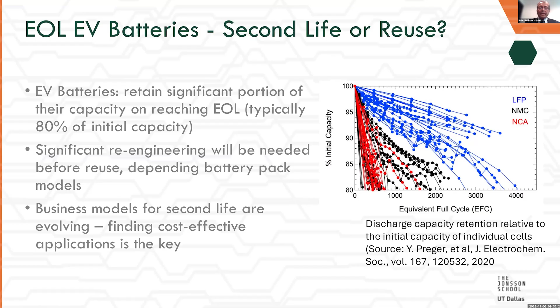But there are common challenges with reuse. We don't know the state of health of the batteries; it varies from cell to cell, sometimes module to module, and cells degrade variably in many cases. You need to look at cell balancing issues, which leads to pack-level stability concerns, so you have to ensure performance is stable from a battery pack. Most of the time, these battery packs are packaged with a proprietary BMS, a battery management system essentially needed for lithium-ion batteries, which is not the case with lead-acid batteries since they don't have a BMS.